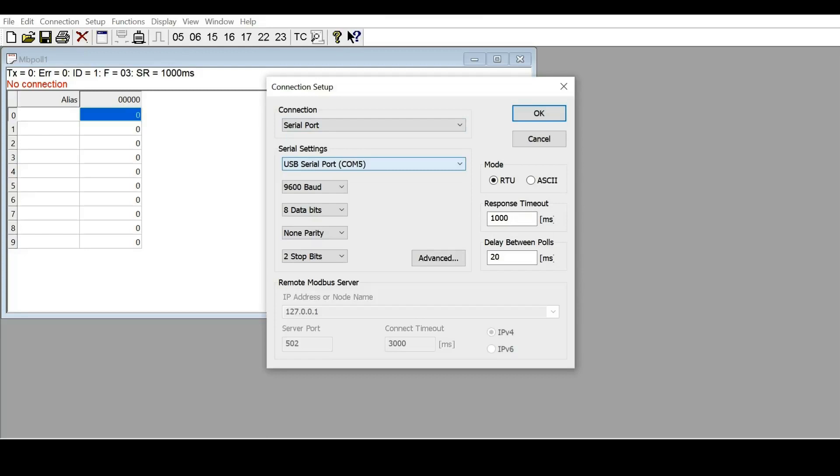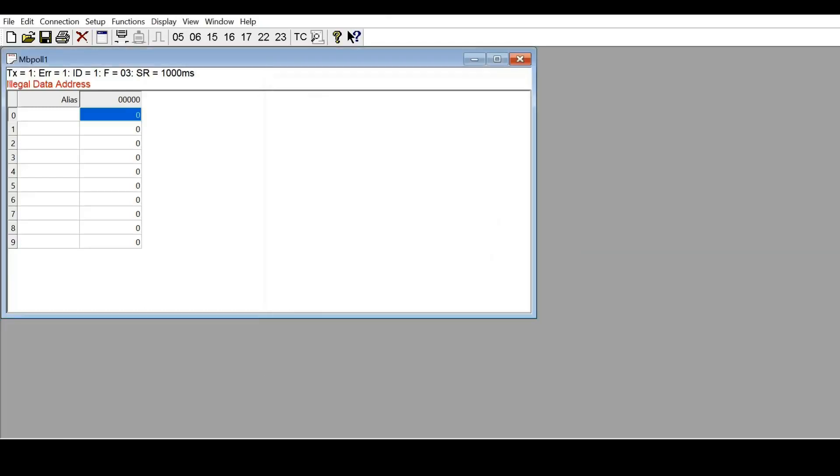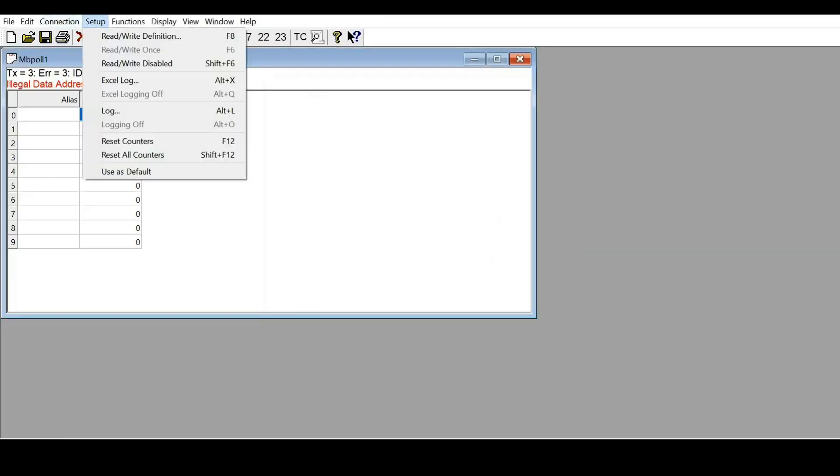to use an RS485 to USB converter to link up with the PC. The baud rate is 9600, 8 data bits, no parity, 1 stop bit, same as the communication settings on the controller. Then the mode is RTU.